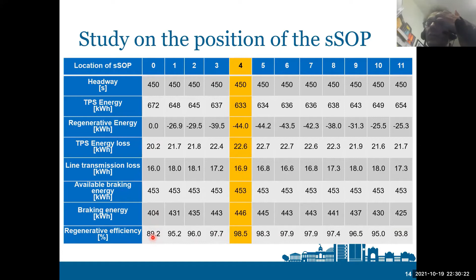We also tried adding a second SOP to the network, and with just two SOPs, the braking efficiency reaches nearly 100%. So generally speaking, there is no need to have SOPs at all traction substations, but it is enough to have around two of them on each rail line to obtain recuperation of nearly 100% of the regenerative braking power.